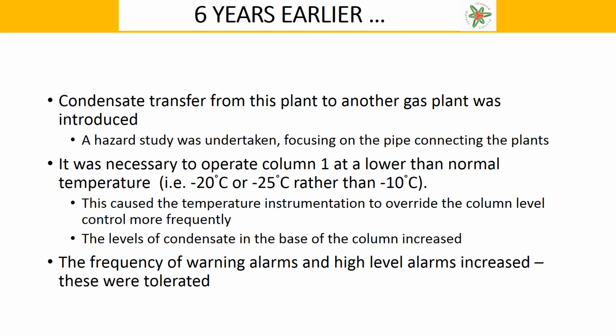This caused the temperature instrumentation to override the column one level control more frequently. Consequently, this raised the level of condensate in the base of column one. Accompanying these conditions was an increase in the frequency of warning alarms. These were for the high-level condensate. These alarms were tolerated.